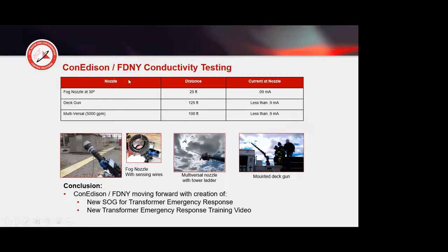And so FDNY has created an SOG, a standard operating guideline, that's available, but with the 30-degree fog nozzle, hang on a minute. Sorry. You could have a standoff distance of 25 feet and not have a current leakage back to the nozzle that exceeds the 0.09. And then with the deck gun, you had to stand back 125 feet, and with the multiversal at 5,000 gallons per minute it was 100 feet.